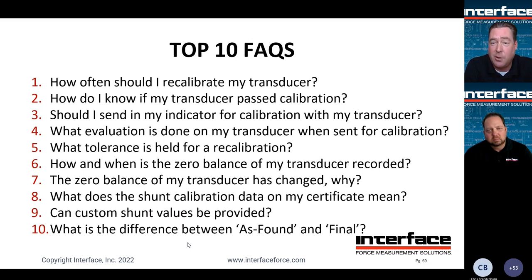If it's a gold standard system, note that you'll want to make sure that you request the indicator be calibrated separately from the load cells, as having a system calibration performed on a gold standard system doesn't accomplish anything, as we need the millivolt per volt data from a load cell calibration to enter into the software.